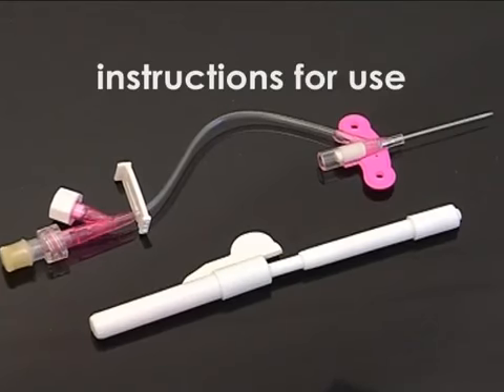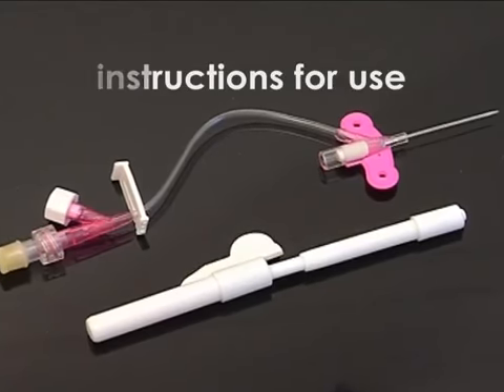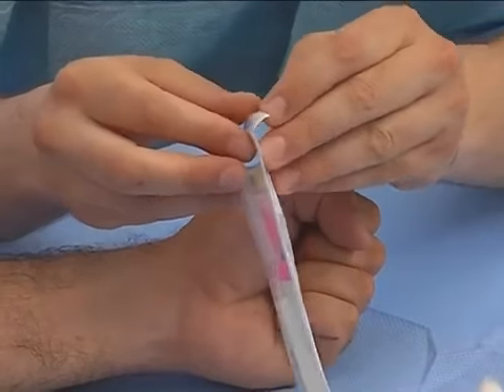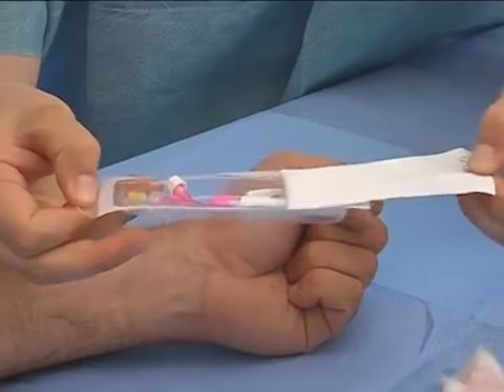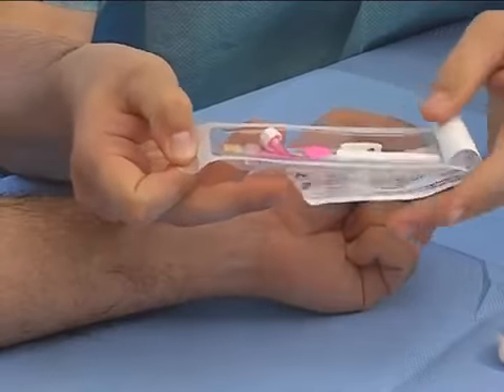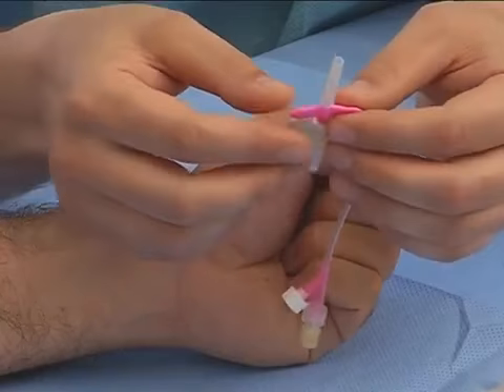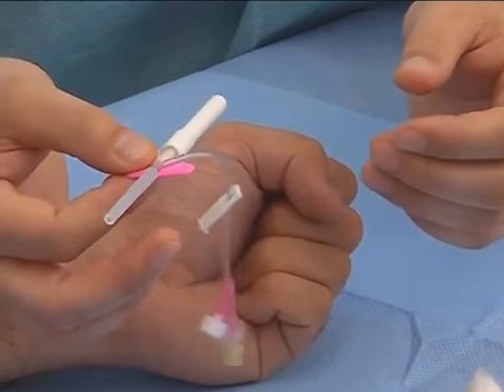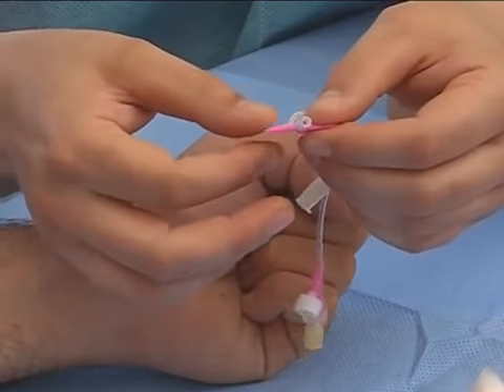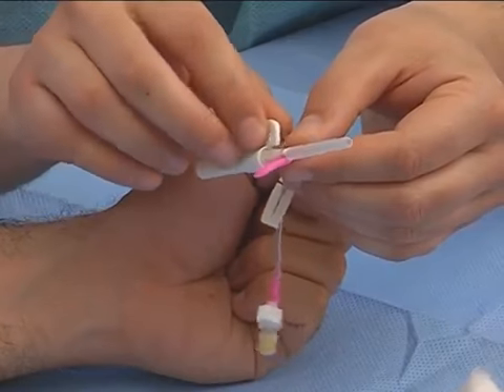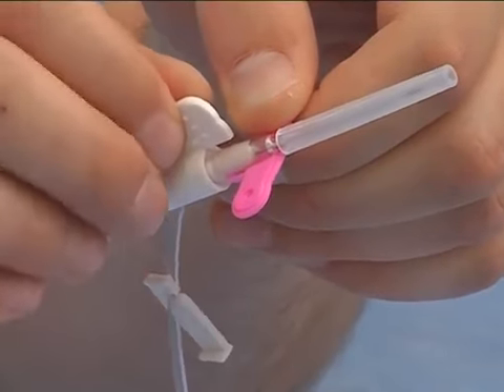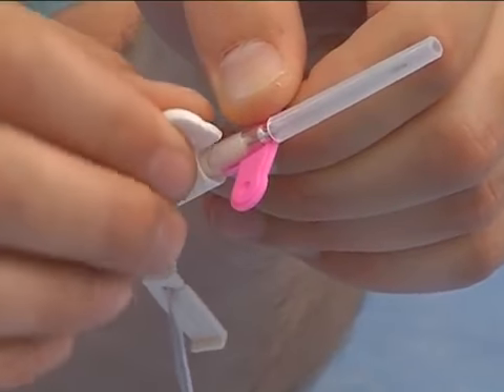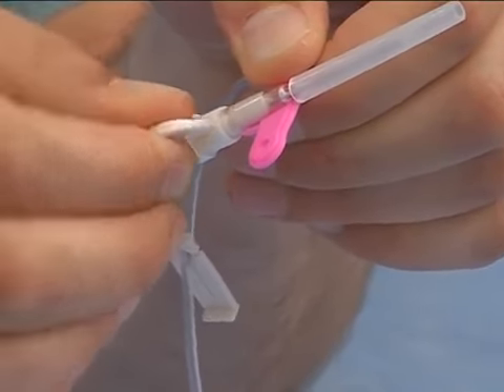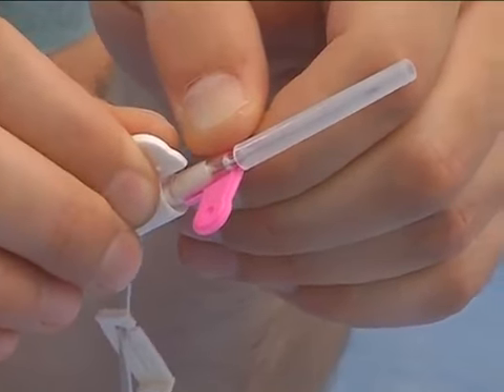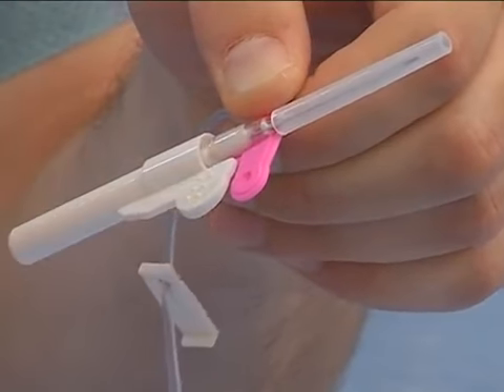Instructions for use. Open the sterile packaging, checking its integrity. Hold the infusion line and the left color-coded wing with one hand. With the other, hold the white wing of the security system. The white wing must be rotated by 90 degrees while being slightly retracted and reinserted to check the proper functioning of the system and facilitate needle retraction after insertion in the vein.